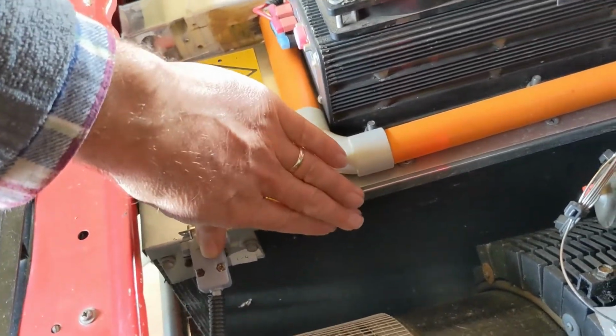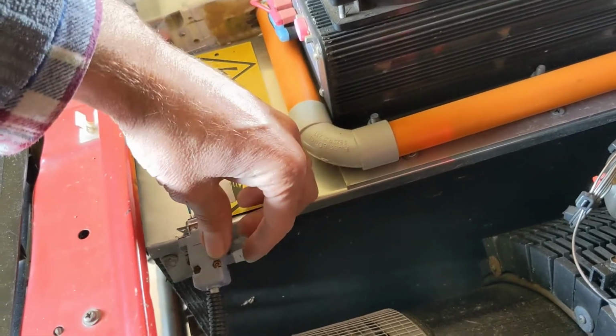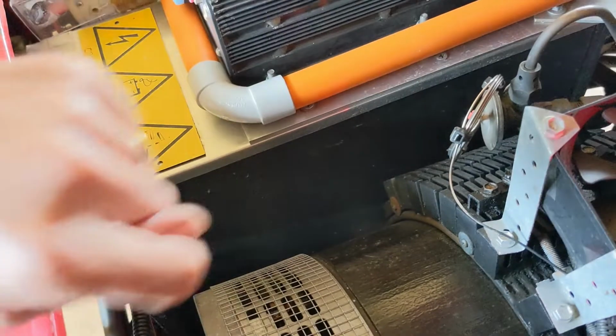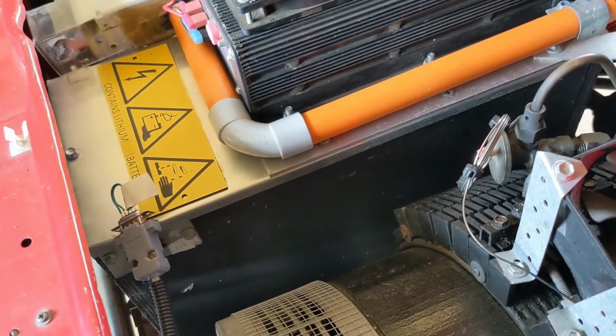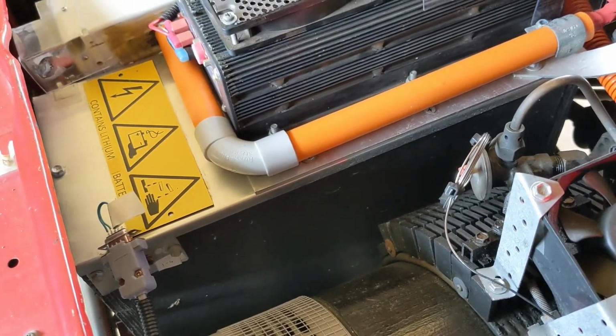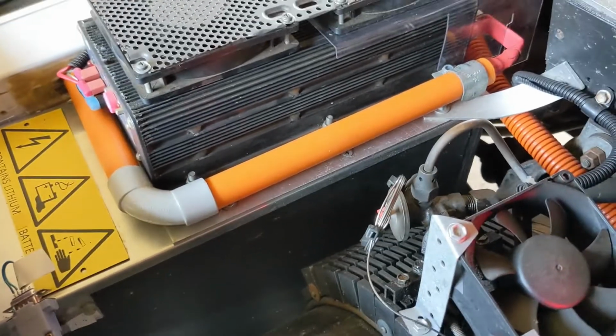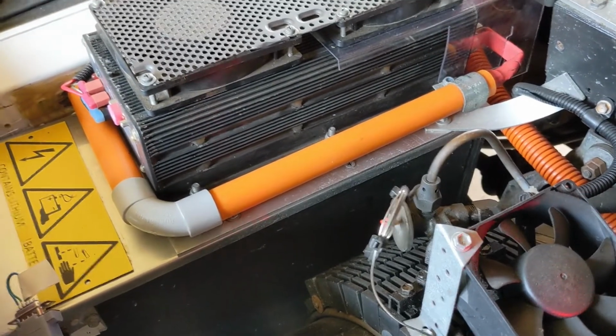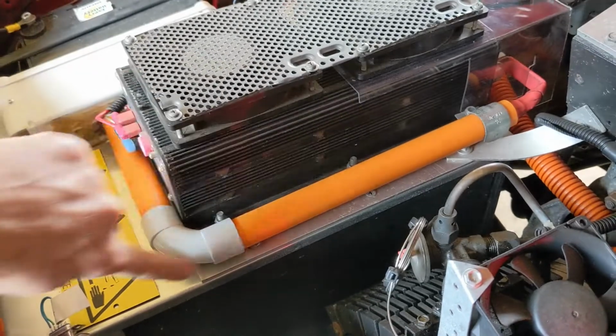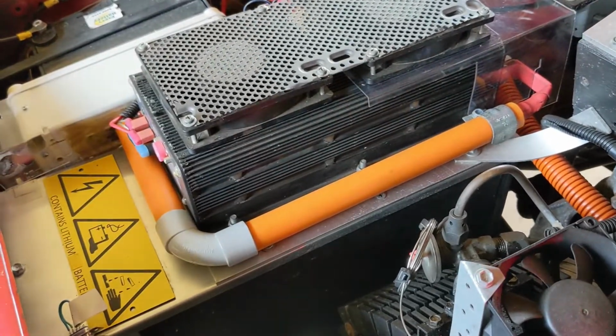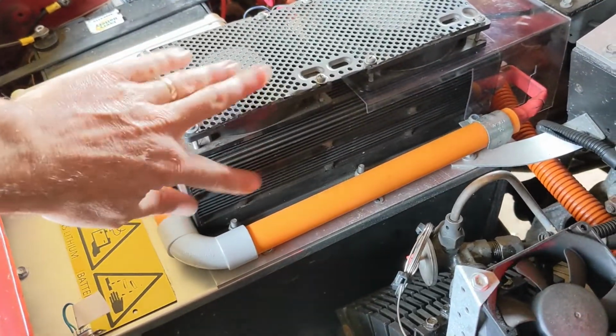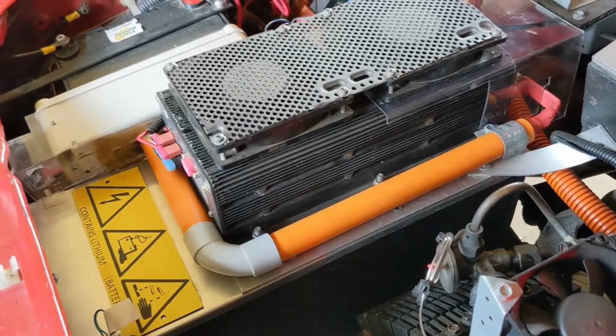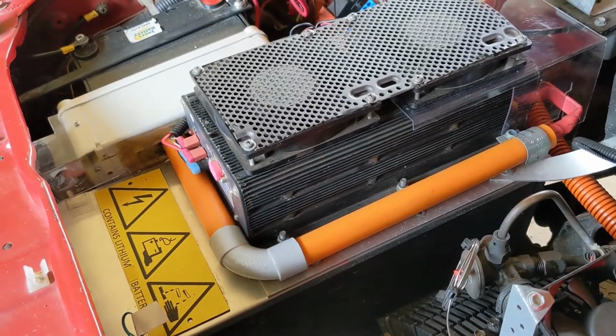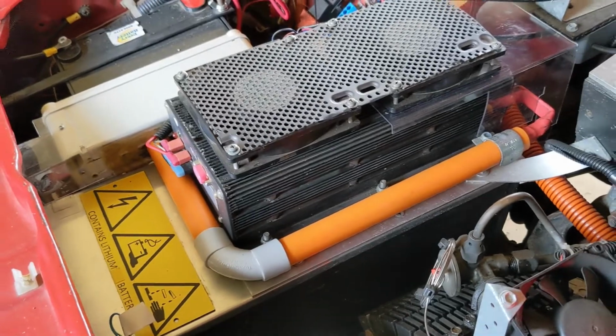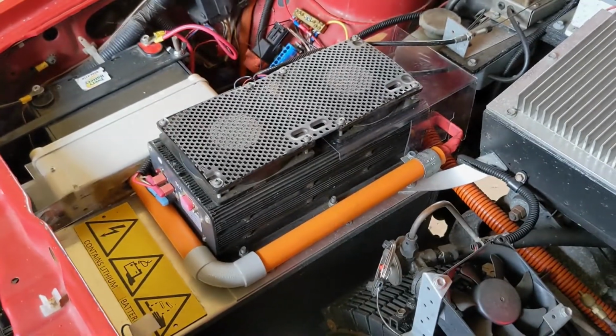I reckon it probably is inside the box, but it would be much easier to shield this cable than it is to undo that box and try and shield individual wires inside there. So there's lots of wires in there and none of them are shielded. There's a couple of obvious ones along the top. Those would be the ones to shield first, but it's probably an hour job to get this off and back on again afterwards. There's lots of connections to undo and do back up again.